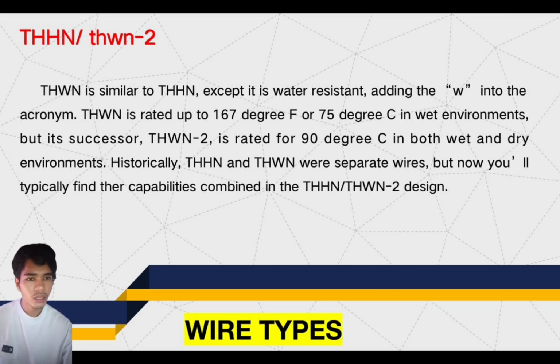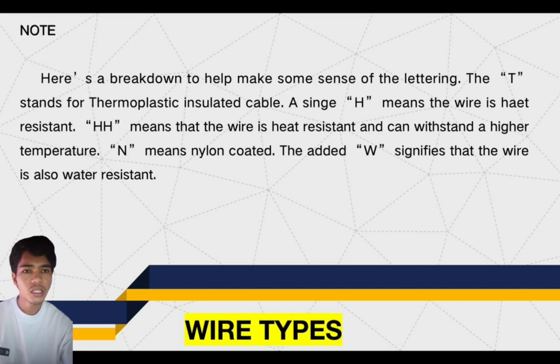Historically THHN and THWN were separate wires, but now you typically find the capabilities combined in THHN/THWN-2 designs. Here's a breakdown to help make some sense of the lettering. The T stands for thermoplastic insulation. H means the wire is heat resistant, HH means the wire is heat resistant and can withstand a higher temperature. N means nylon coated. The added W signifies that the wire is also water resistant.